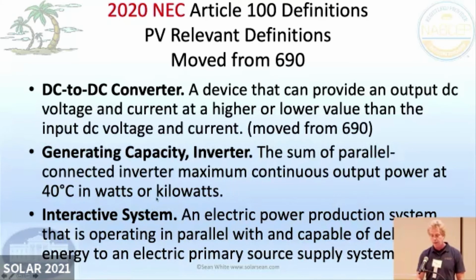Inverter generating capacity, that's the AC output of an inverter. So if you're over 100 kilowatts, you get benefits for PV systems under engineering supervision, and you could use different values for current and voltage. And if you're over 5 megawatts for a ground mount, you can use Article 691. So that's like, you know, utility scale and all that. Interactive just means it interacts with the primary power source, the grid, so it could feed the grid.